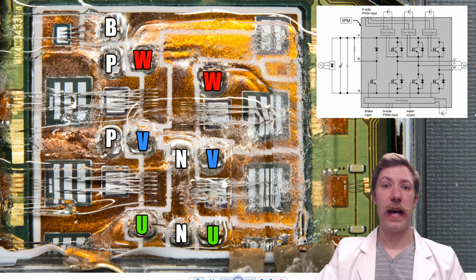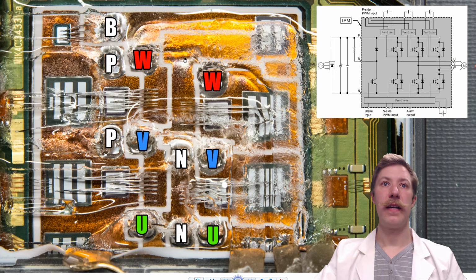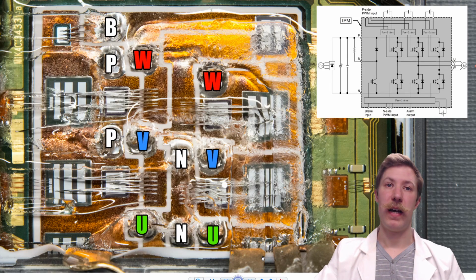With the schematic at hand up here in the right corner, we can now walk through the circuit according to the schematic. Now if we start with the positive input, I have marked those up by P, and as we can see that goes to the high side collector part, and we have IGBT 1, 2 and 3 of the upper side of the three-phase full bridge sitting here in the left side. Now the negative supply goes in here at N, and this supplies the emitter part of IGBT 1, 2 and 3 of the three-phase full bridge low side.